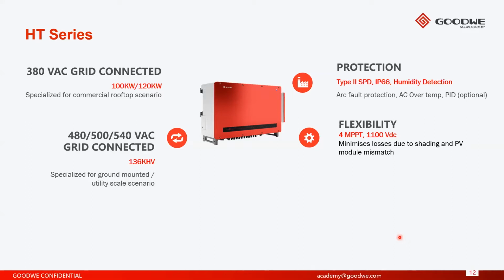The 136 kilowatt version is the high voltage version, which can be connected to high voltage networks or to a step-up transformer, which can accept a 480, 500, and 540 volt AC input. So this inverter has been specially designed for ground-mounted and utility scale PV farms. So this unit, we believe, is the one that will be quite attractive for Poland in terms of the 1 megawatt tender auctions that we are seeing at the moment.